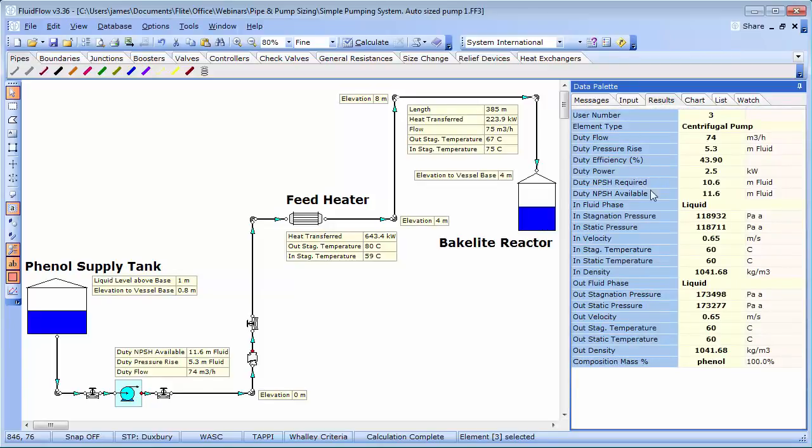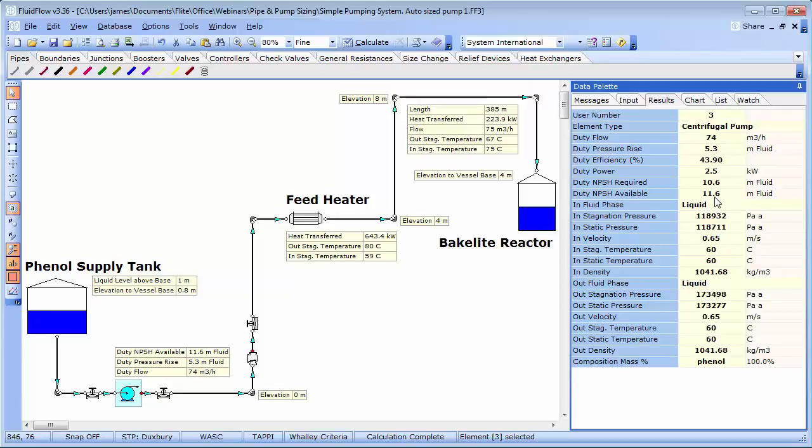And we can see the NPSH required is 10.6 meters of fluid. And that available is just slightly over at 11.6 meters of fluid. And the hydraulic institute recommends that an NPSH margin, that's the ratio of net positive suction head available, divided by that required by the pump, of the range 1.1 to 2.5 depending on suction energy levels, is an ideal operating scenario.